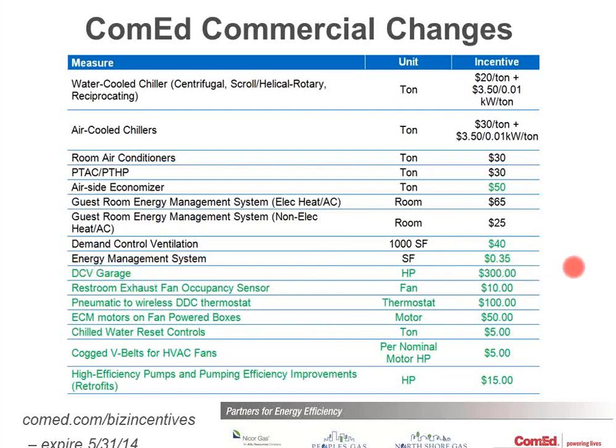There's a lot of rules associated with that program. I'll touch on a few of them in a minute. If you put demand control ventilation in a parking garage, it's $300 per exhaust fan horsepower. Once again, you're using CO or nitrogen dioxide sensors to ramp up and down that fan. There's a small new rebate for adding occupancy sensors to bathrooms. Basically turn the bathroom exhaust fan off when no one's in there. You could add ECM motors to a fan power box and get a rebate. However, I will caution you on that. The spec for that for ComEd says that you actually have to control the speed of the fan.